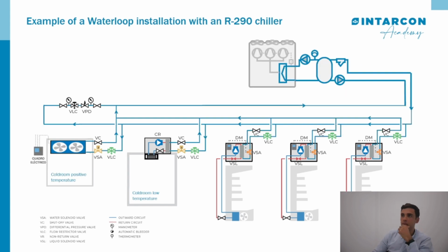In this slide, we have a variation of the Waterloop system where we use a water chiller. The chiller in this case would be, for example, with propane that we incorporate for cooling the Waterloop installation. So we can supply different equipment and also different cool room needs. For example, for positive temperature, we could have an air cooler to ensure properly the cooling efficiency in this cool room. Here we can see a mixture between a chiller system and a Waterloop system.